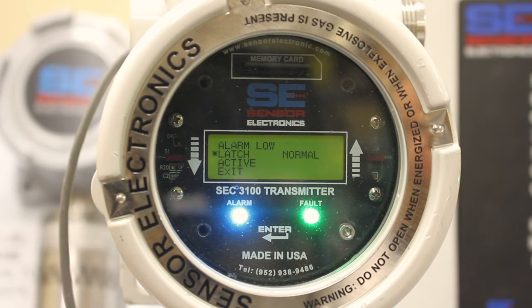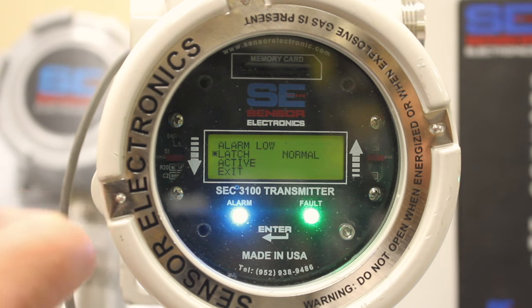And you can also program the relays to be latching or non-latching. Normal is non-latching, so once an alarm is reached, it goes above that alarm level, the relay is energized, and then once it goes below that alarm level, the relay de-energizes. And to change latching, also you can program it to be an audible alarm.